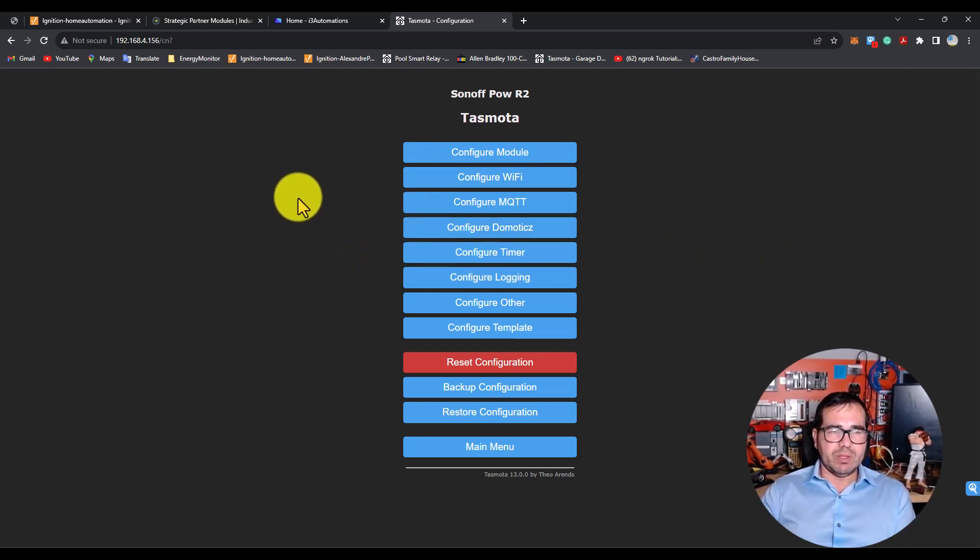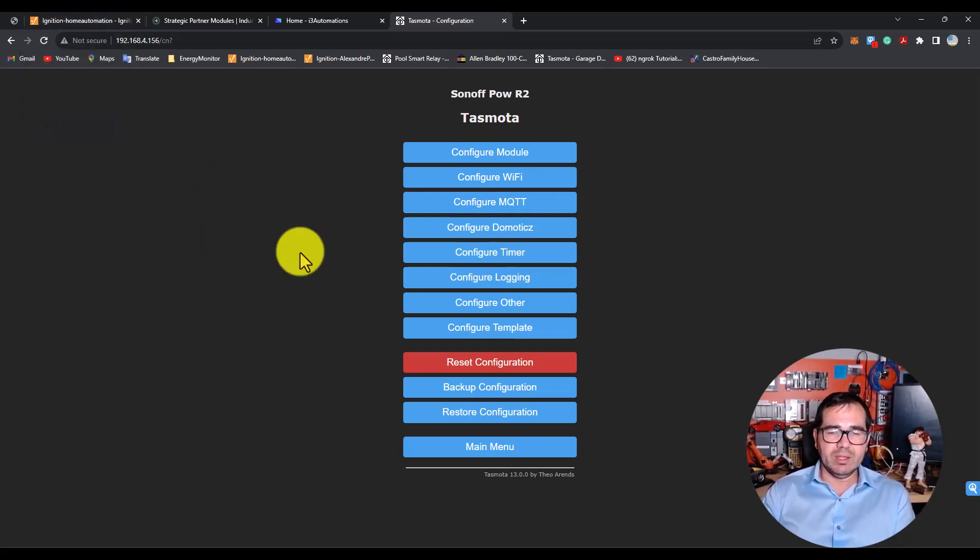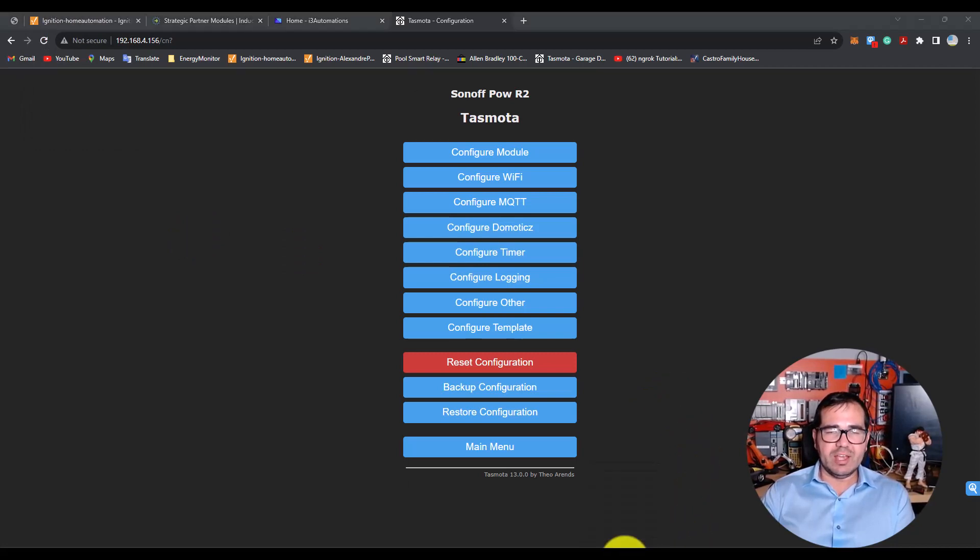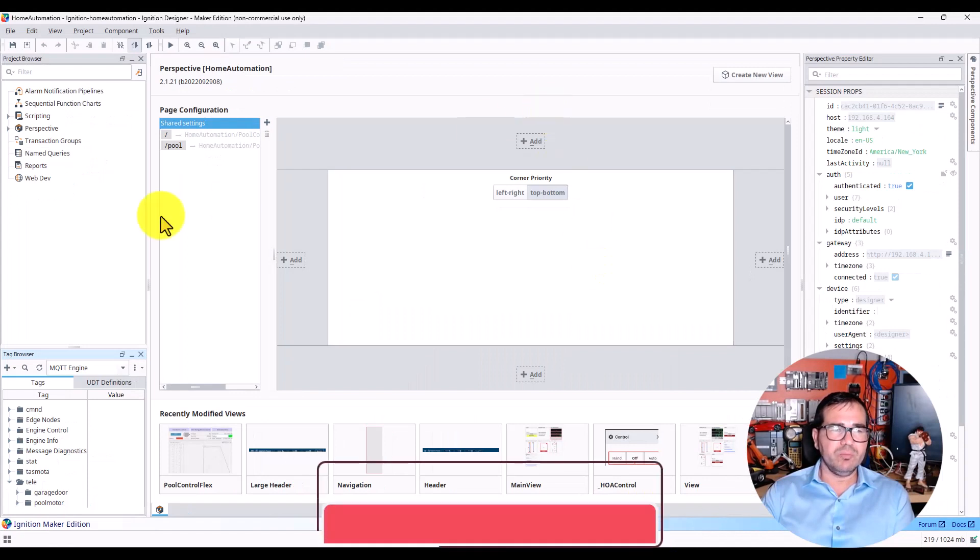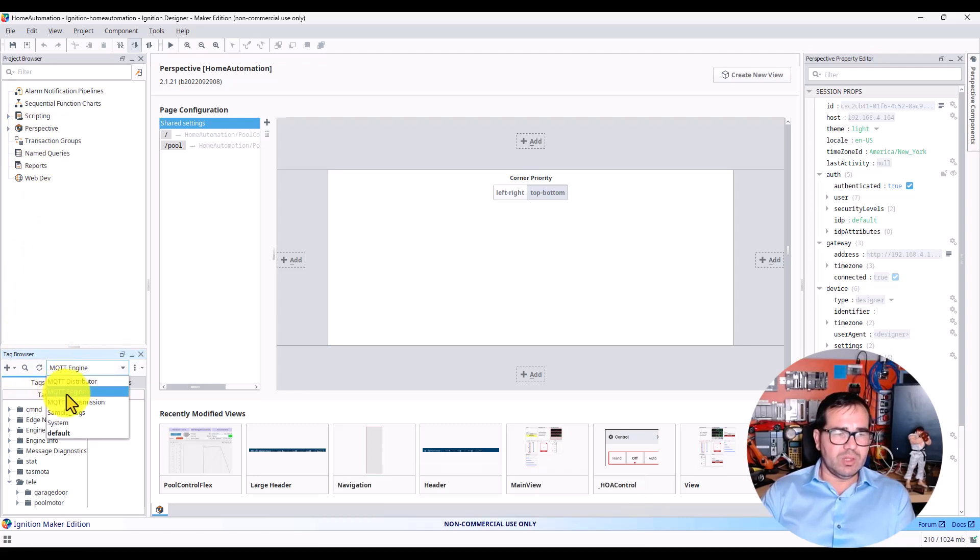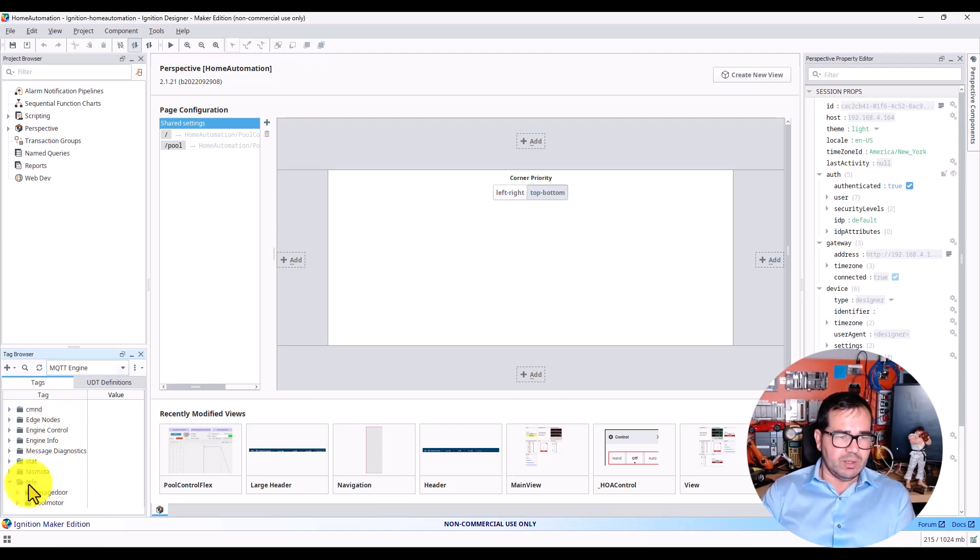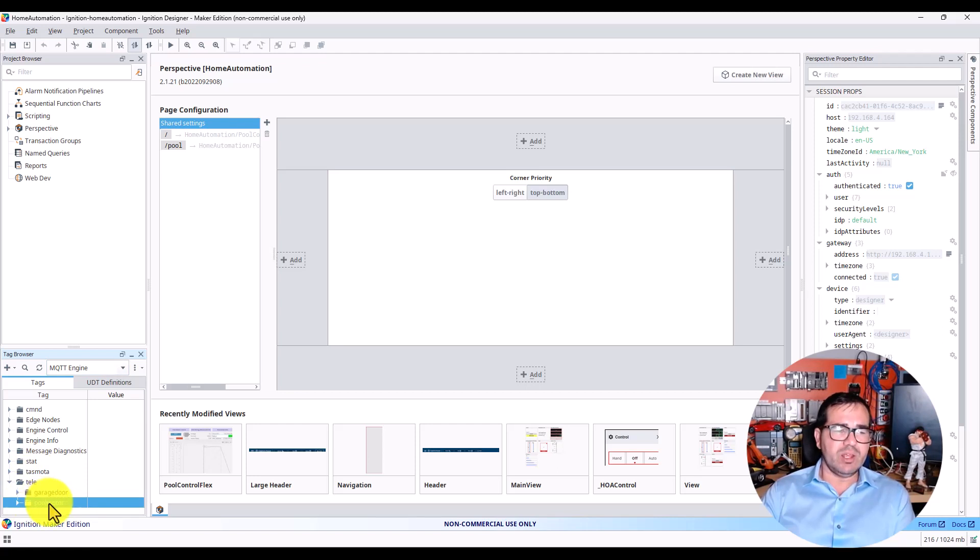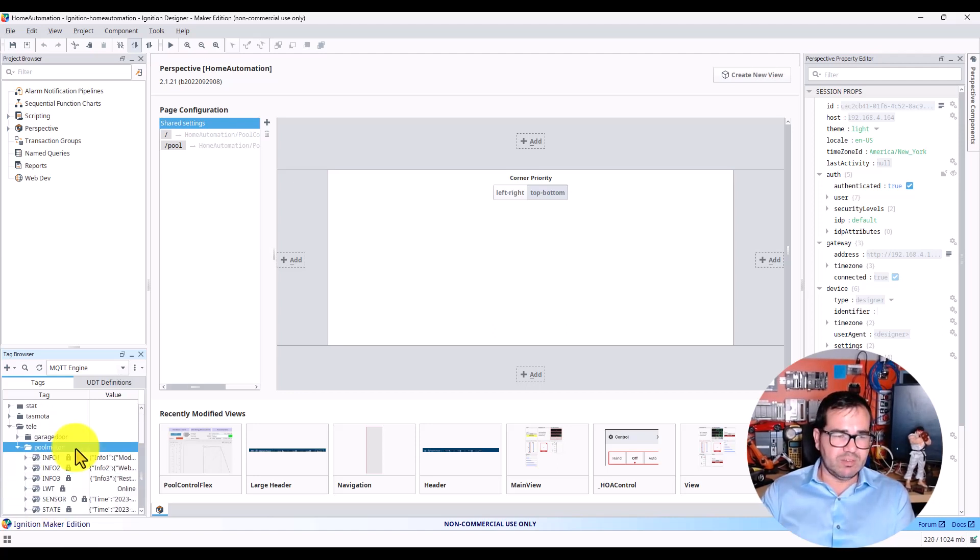Now to make sure your MQTT is working and your Ignition can see the MQTT configuration automatically, you need to open your Designer. I already opened Ignition Designer here. On the tag browser, go to MQTT Engine, and here you should see 'pool motor'. That means Ignition has already subscribed to this topic, which is why we can see it here.